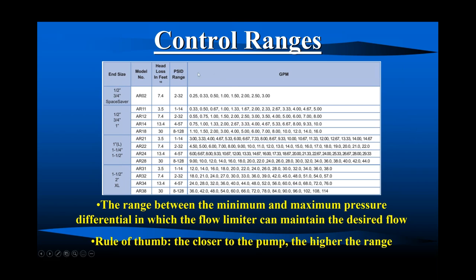So let's talk about that briefly. This is our PSID range, 2 to 32. That's 2 to 32 PSI. I would say 95% of all flow limiters leave the factory with this range in it. 32 PSI being roughly 75 feet. So if you have a pump that's 250 GPM at 75 feet, all those flow limiters in that system are going to get cut for whatever GPM you need, but the pressure range is going to be 2 to 32.